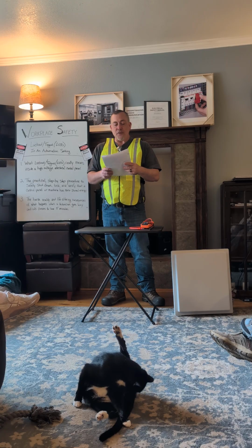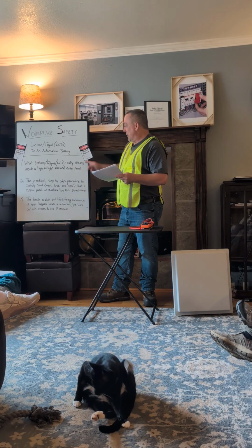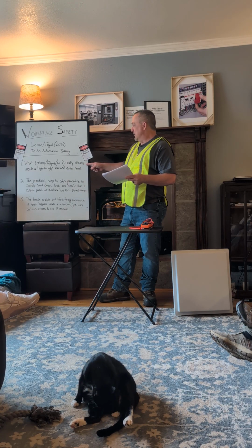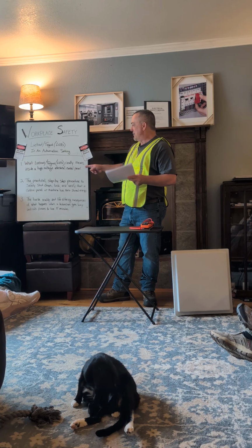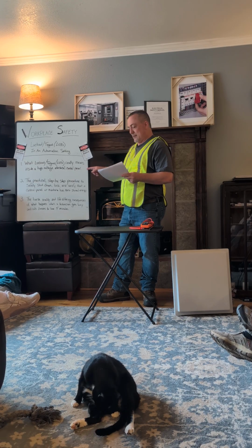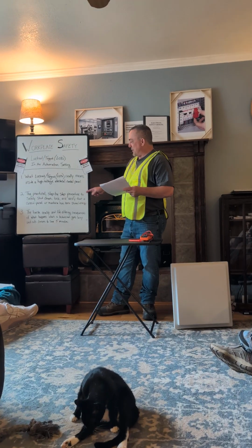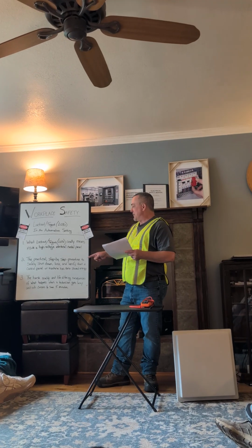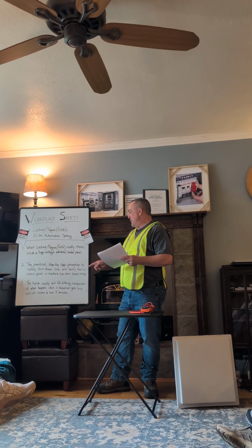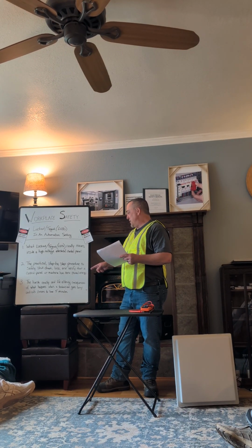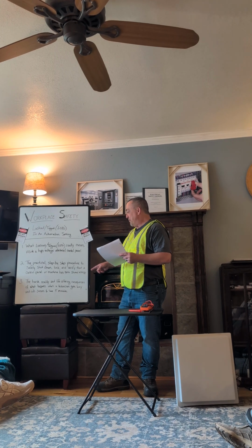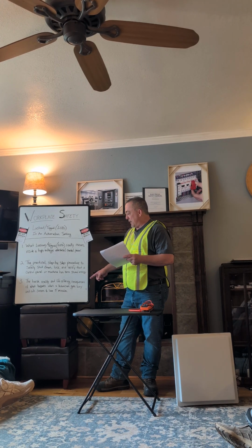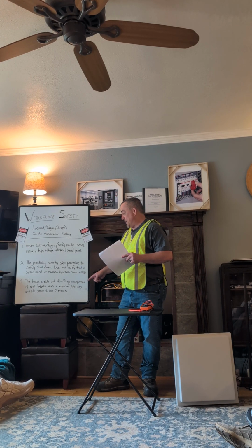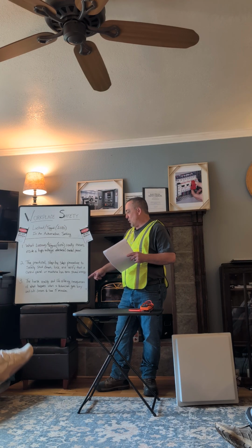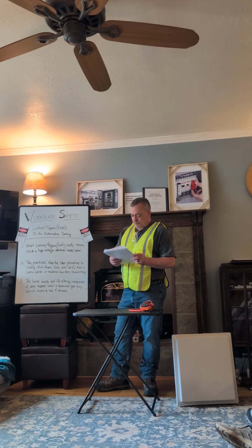Today, we're going to look at three main things. Number one, what is lockout-tagout, and what it really means inside a high voltage electrical control panel. Number two, the practical step-by-step procedure to safely shut down, lock, and verify that a control panel or machine has zero stored energy. And number three, the harsh reality and life-altering consequences of what happens when a technician gets lazy and cuts corners to save 5 minutes.